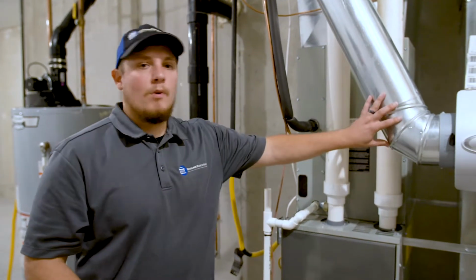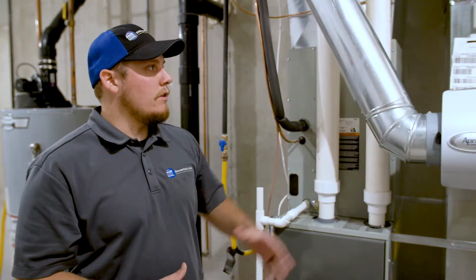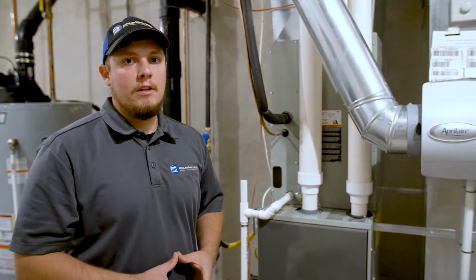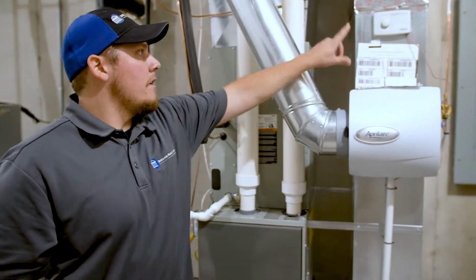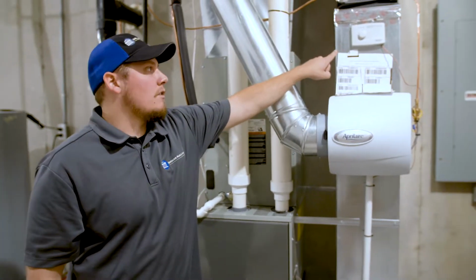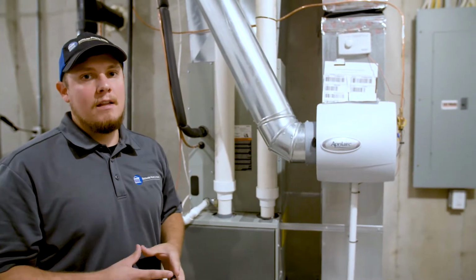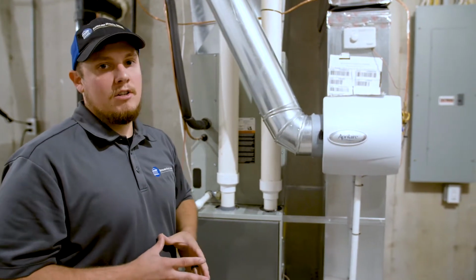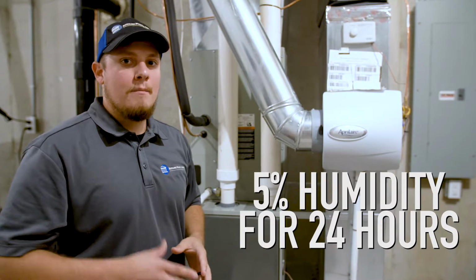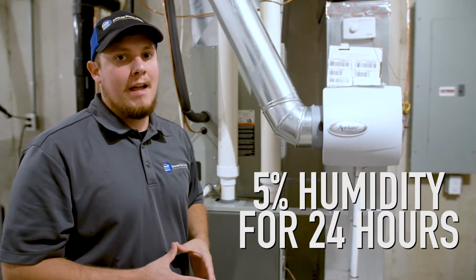This furnace here is also equipped with a humidifier. If you elect to do the humidifier in your home, there's a few things that you need to know about it. First off, this is the control for the level of humidity in your house. It is working on 5% intervals. You only want to change your humidity in your house 5% at a time and then wait for a 24-hour cycle for that to take effect.